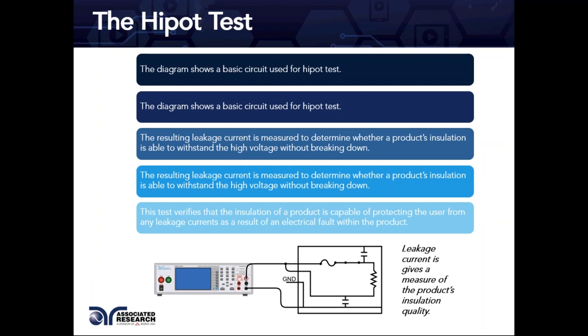The resulting leakage current also indicates the quality of the insulation. Application of high voltage across any insulation barrier will result in some leakage current trying to flow through it — that's what insulation is meant to prevent. By analyzing the leakage current, engineers can determine whether the insulation is adequate and will protect the user or anyone coming in contact with the device.